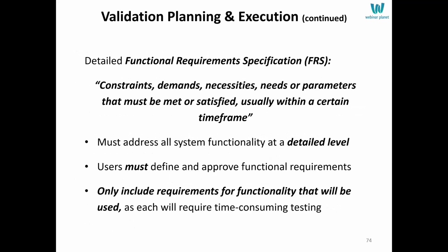Based on the URS, you're going to break that down into very detailed, granular functional requirements. Every function at a detailed level. And users should define and approve these. But again, they don't have to approve them all before you start work, before your vendor starts work. Only include requirements for functionality that you're going to use.